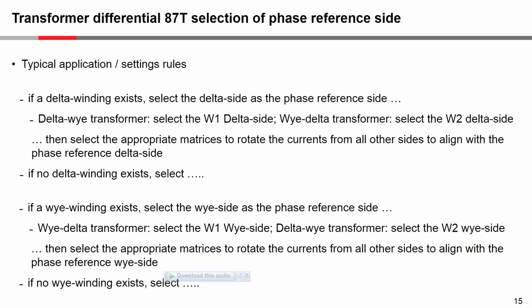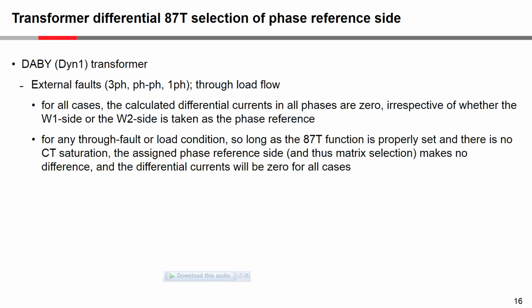Okay, so let's have a look a little bit further. Firstly, for all external faults or through load current, the calculated differential currents in all phases are 0. We're talking about faults through the transformer now, not internal faults, something that is passing through the transformer. So the differential current will be calculated as 0, irrespective of whether the winding 1 side or the winding 2 side is taken as the phase reference. So dig a little bit deeper on that. For any through fault or load condition, so long as the 87T function is properly set and there is no CT saturation, the assigned phase reference side, and by assigning the phase reference side I mean selecting what matrices will be used, makes no difference, and the differential currents will be 0.